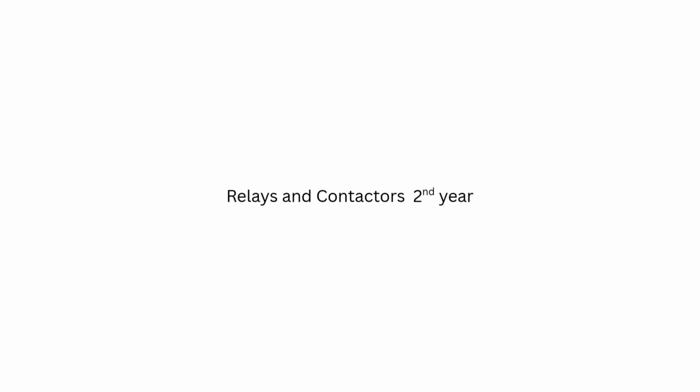And for anyone troubleshooting, there's a key detail to remember: for every NO/NC contact set on a plug-in relay, you need 3 pins. One common, one NO, and one NC.